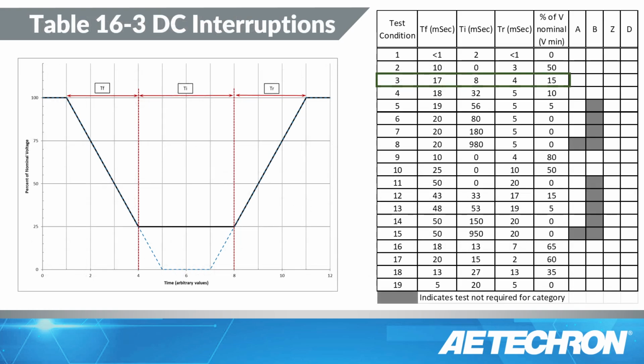Let me look at the momentary interrupt test here. This is from table 16.3, which is for the DC portion of the momentary interrupts. In this case, you're going to notice my table here is vertical, and we're going to provide that table vertically in DO160H. Currently, it's horizontal. It makes it a little tough sometimes to look at a test condition and look down on a table to figure out what's the fall time, the dwell time, the rise time, and to what percentage you are performing the test. Let me look at test condition 3 here, and I'll define some of this for you.